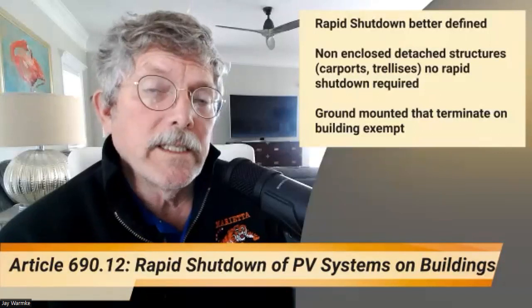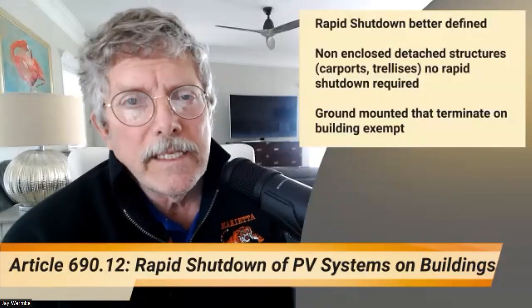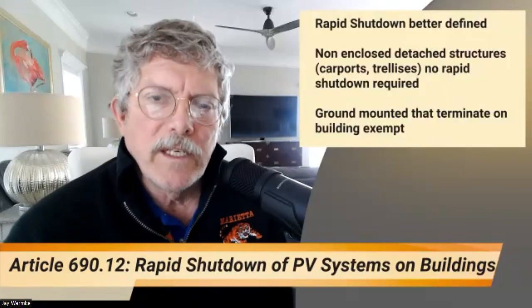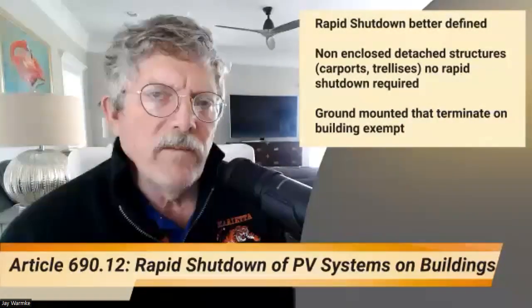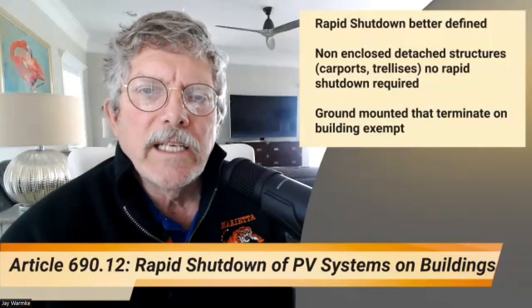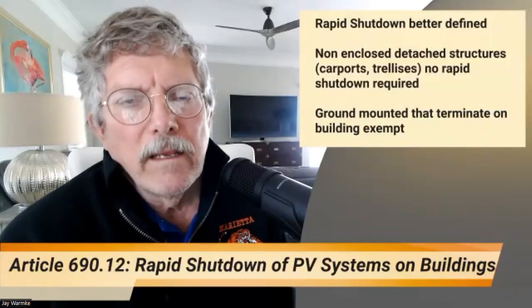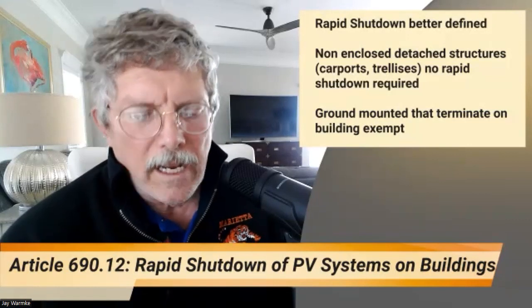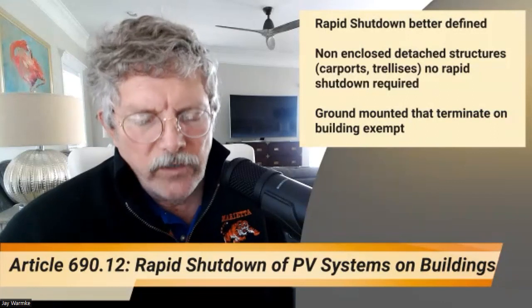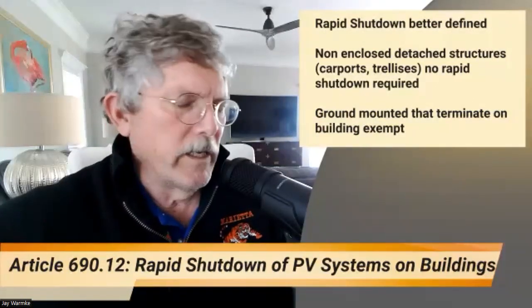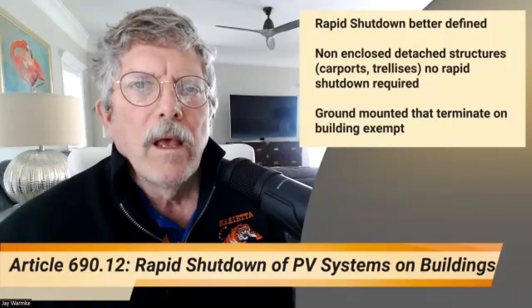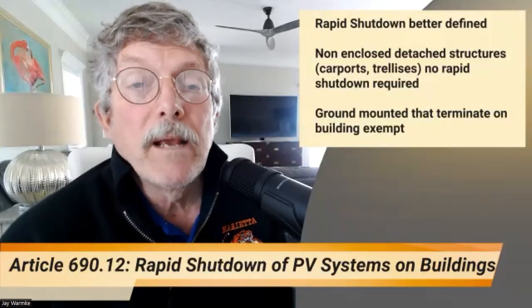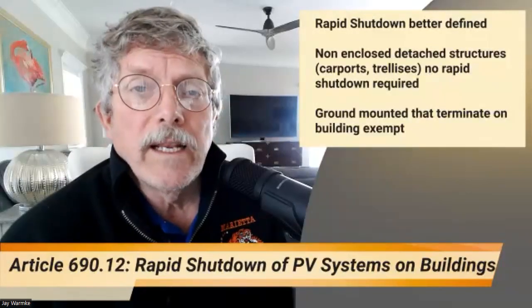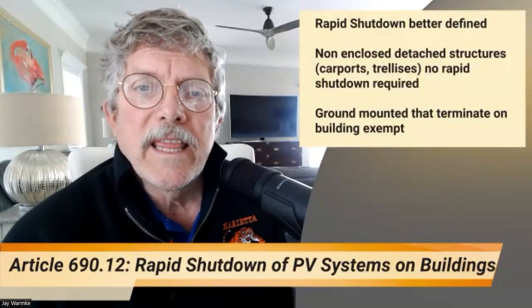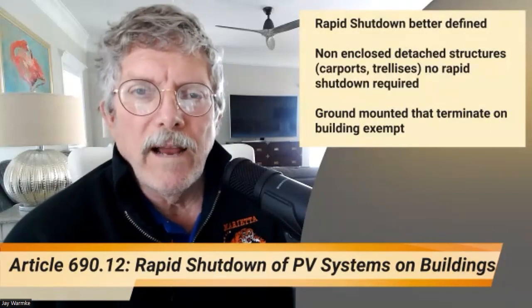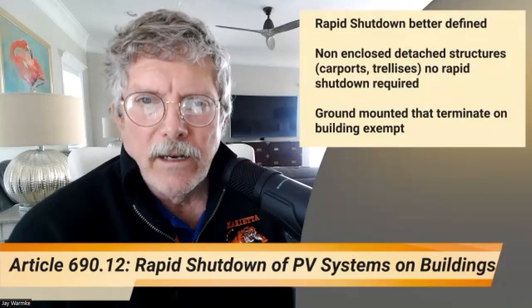Then no rapid shutdown is required. So rapid shutdown in this instance typically means that when you turn off the disconnect switch, the main disconnect for the PV array, the energized conductors stop at the array effectively. There's a lot of other things there, but it's got to be within 1 foot of the array boundary, no more, no power greater than, trying to think, I think it's 30 volts. That might not be right. But anyway, basically, it's so firemen are not injured or killed because they think that the power is off, but then they cut through a live wire. So they want that to shut down at the array.